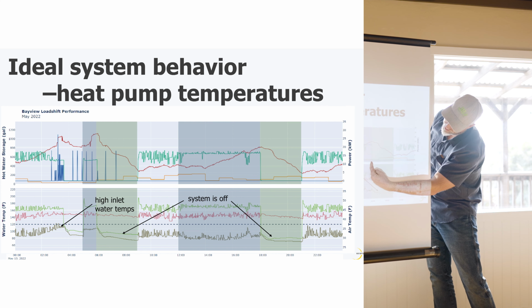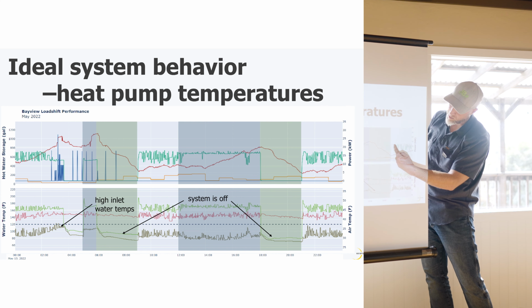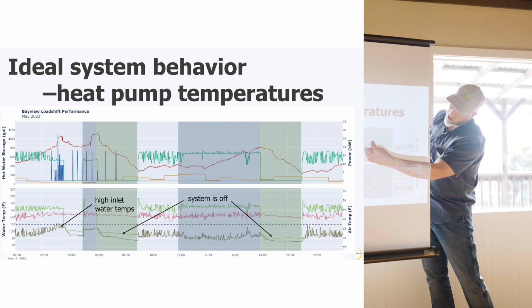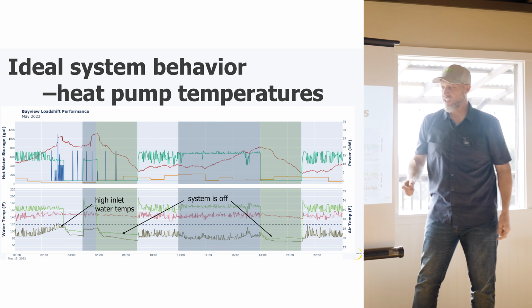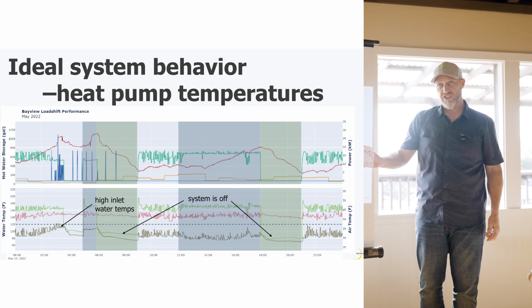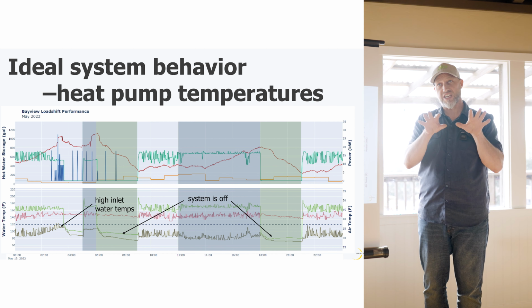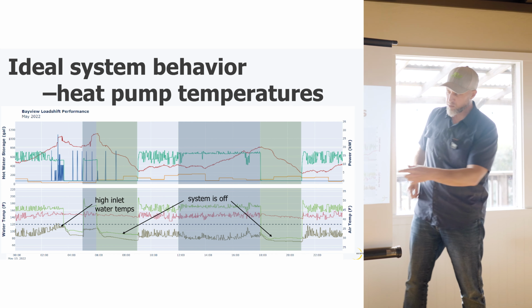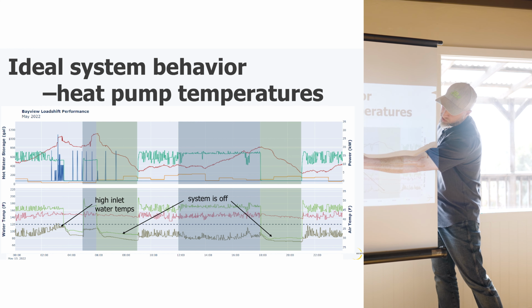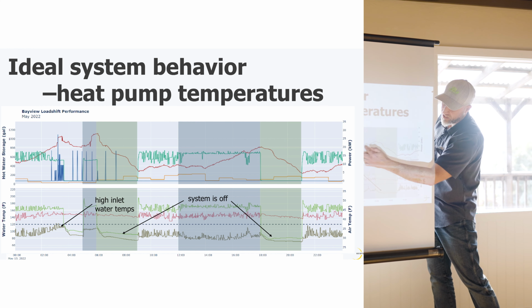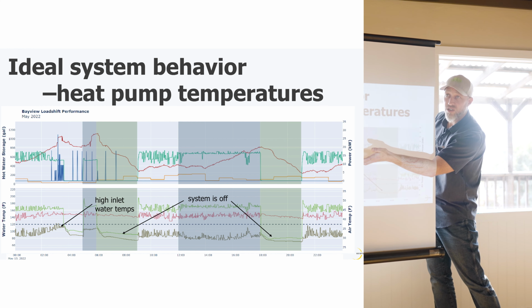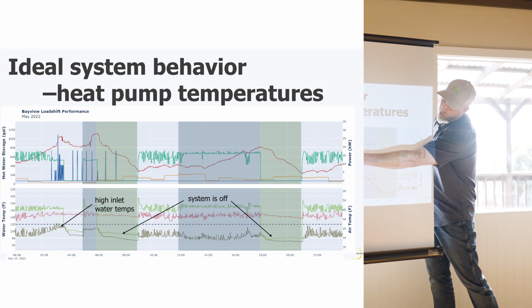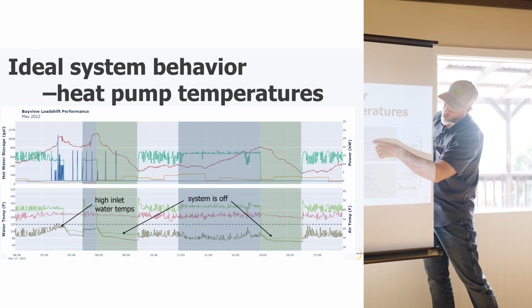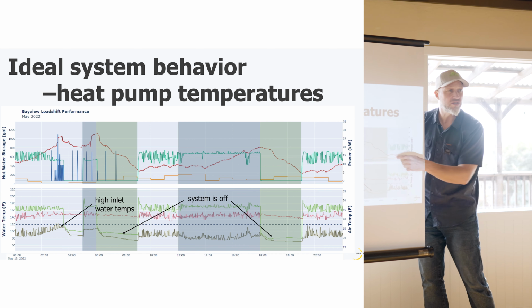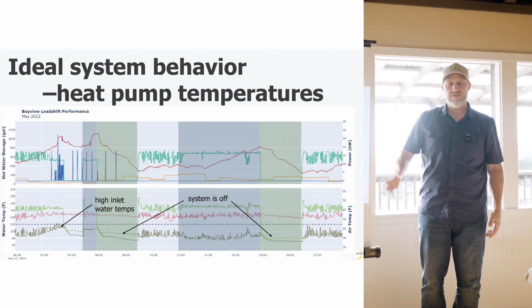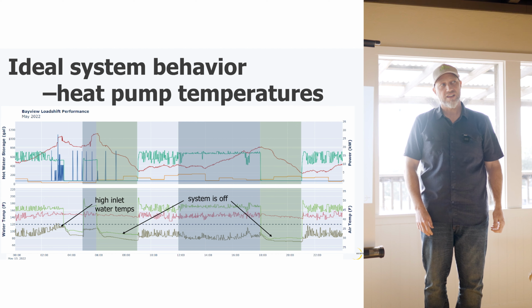We turn it off completely for 4 hours, then turn it back on, so we're buffering it up and can pull through. We're doing this with the Mitsubishi unit, we had to write some code to initiate changing the temperature. In this load up period, we moved the temperature from 150 to 170 for capacity reasons. We tell the Mitsu to output full, then turn it off and let it coast through the peak. We have this building running this way right now.